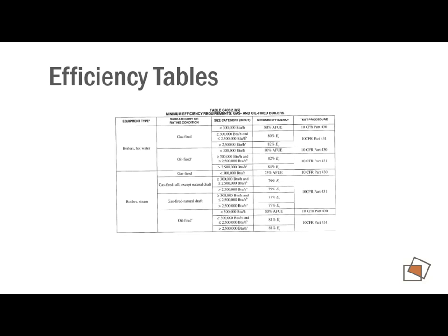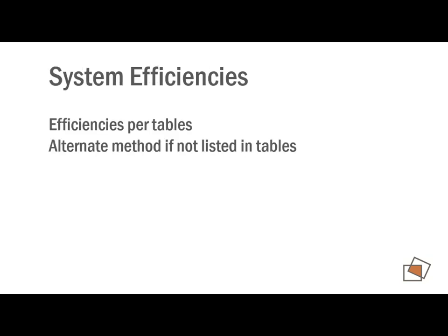A lot of this is handled on the manufacturer side, on the SEER ratings, on the air conditioners. We're seeing those pushed up and up and up as the requirements are raised and tightened on these manufacturers. So they're getting easier to hit in some cases. And the fact that we've adopted the 2012 here rather than 2018 probably makes it even a little bit easier for us to hit some of those. So there are equipment efficiency minimums that we have to comply with. It also gives a method where we can do our own calculations if whatever we're designing is not listed in that table.